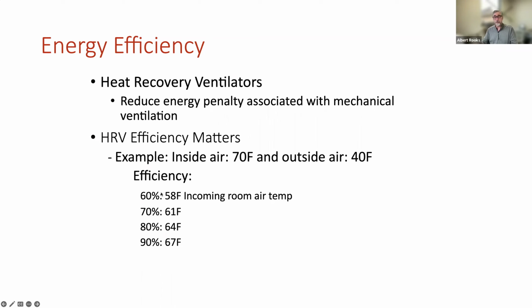In the extreme parts, cold and dry or hot and humid, we might have to add a little bit of cooling or dehumidification on the building to kind of control it. But in the midsections, we can control it pretty well with the quality of enthalpy recovery and the flow rates that we use. So flow rates also have a lot to do with basically the energy penalty and how efficient of an HRV that we choose.